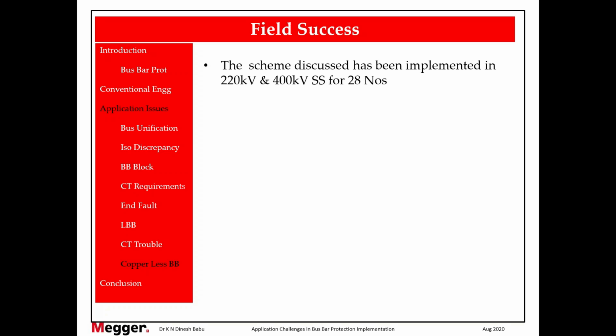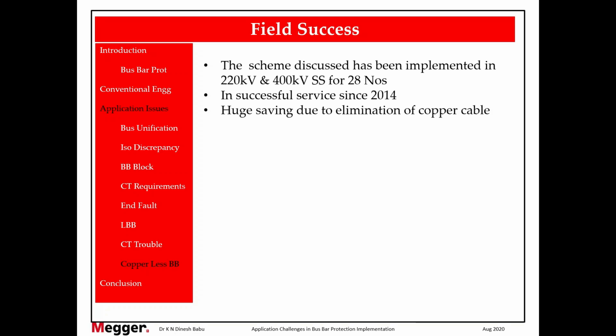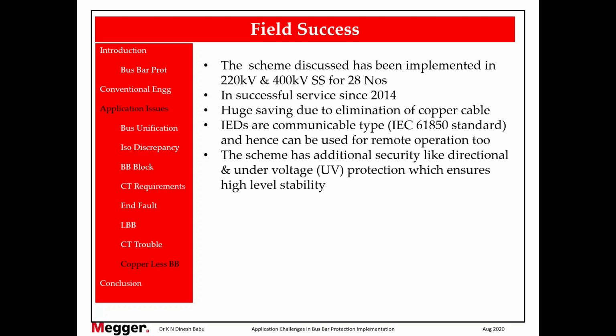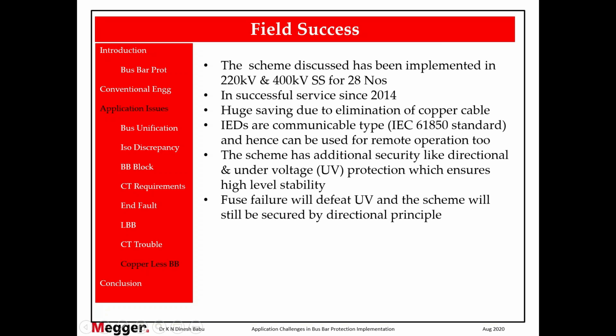Okay, so I'll just conclude, sir. Whatever we discussed right now is not just a theory. This has been implemented successfully in more than 28 substations in MPPTCL and tested, and it has been in successful service since 2014, which has resulted in huge saving through copper cable elimination. In addition to the trip logic which we discussed earlier, this undervoltage bus protection is also implemented. So any kind of wrong selection, all these things are addressed using the additional security level here.